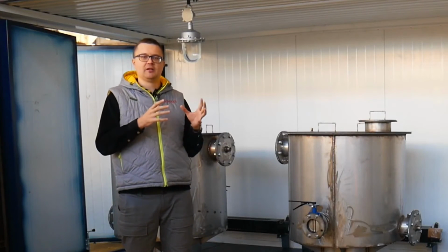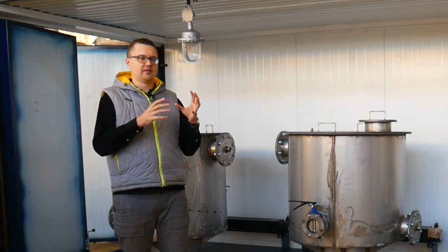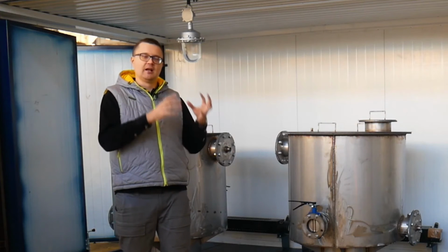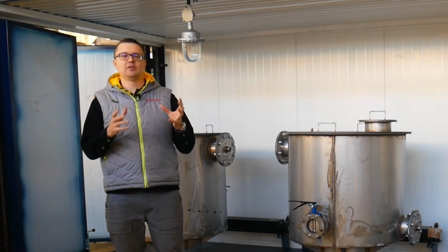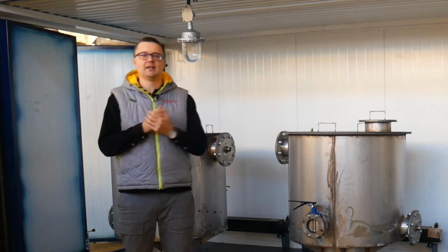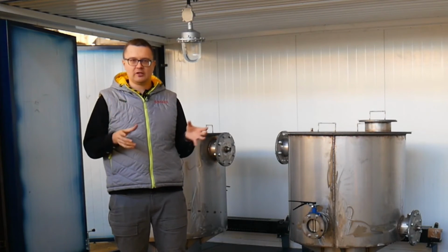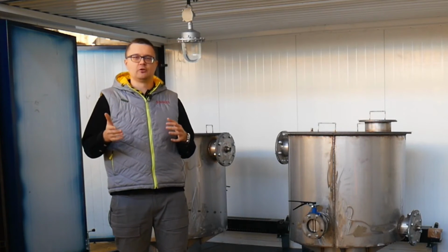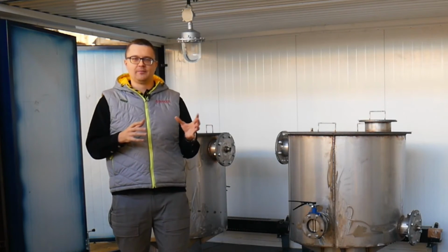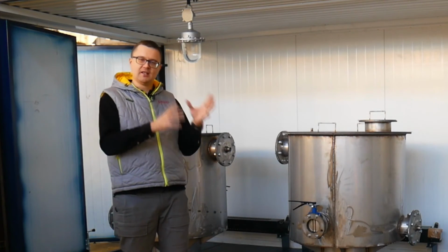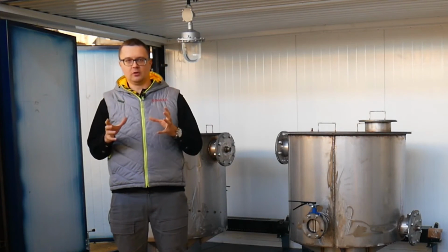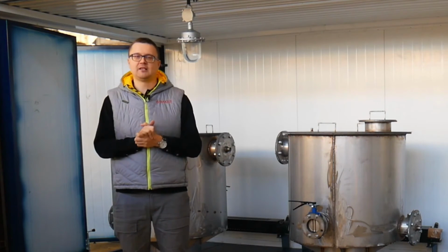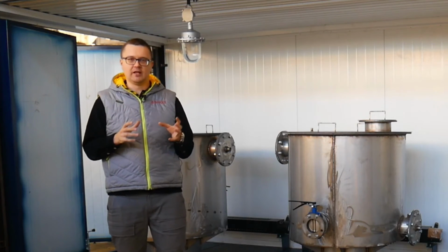For example, the percentage for some sorbents totals 0.5, 1%, 5%, 18%, and 20%. This is the factor which directly affects the efficiency of the adsorber and how durable it is in operation. That is, some sorbents may clog, roughly speaking, in a week, while others will work for 6 months. This should be carefully considered when selecting the appropriate equipment.